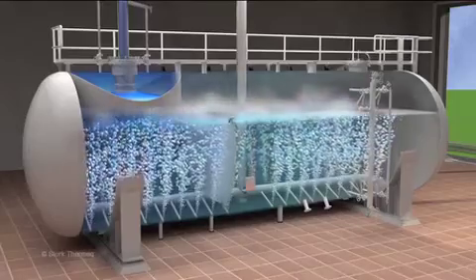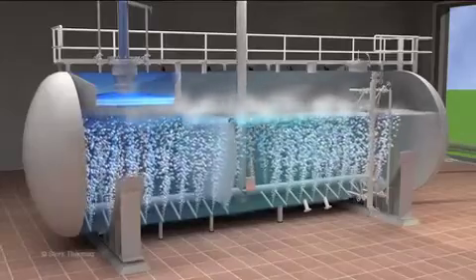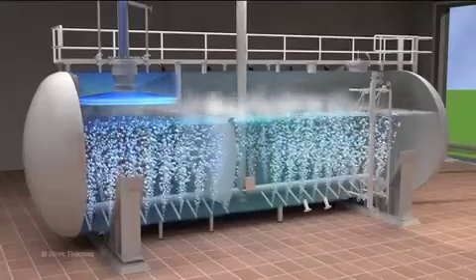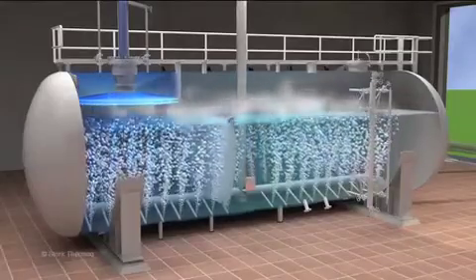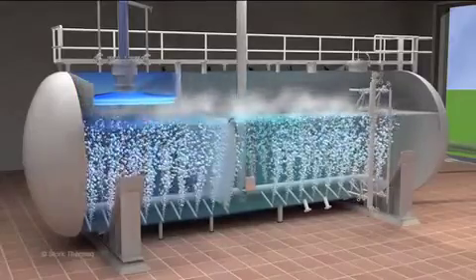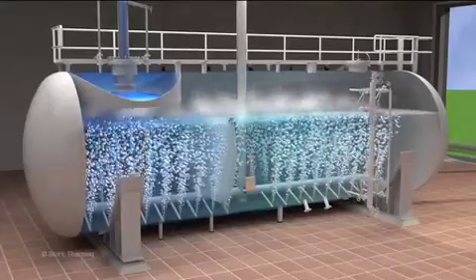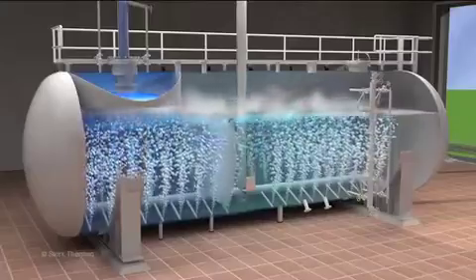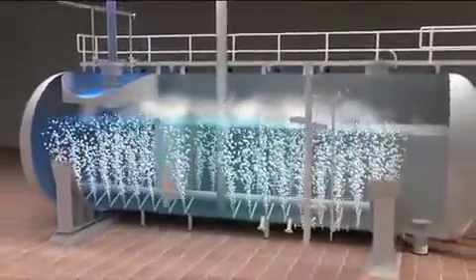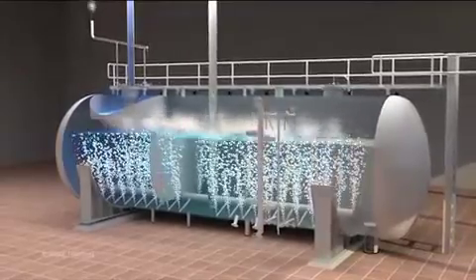The Stork deaerator can achieve a reduction of oxygen concentrations to levels below 7 ppb without oxygen scavengers. The sprayer assures heating up to condensate desaturation temperature, and the pre-deaeration takes place in this area. The Stork deaerator ensures a good contact between water and steam, allowing non-condensables to move from the water to the steam. Finally, the non-condensables are vented into the atmosphere with a minimum vent loss.